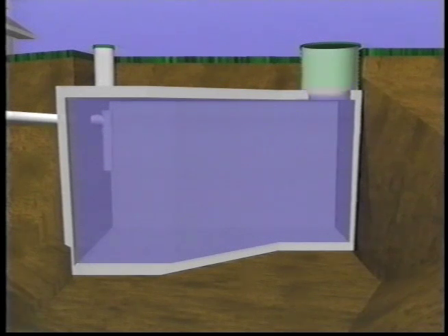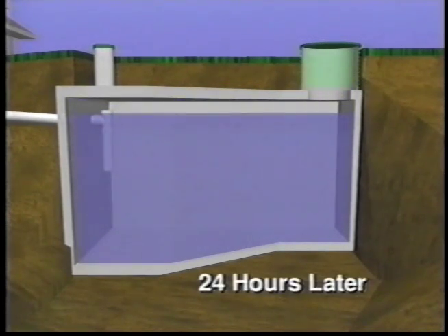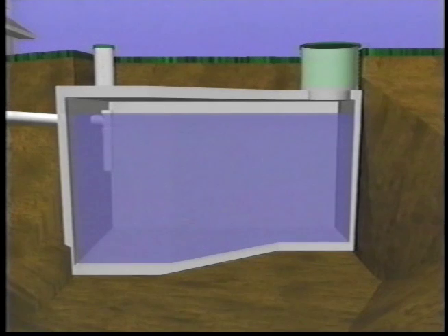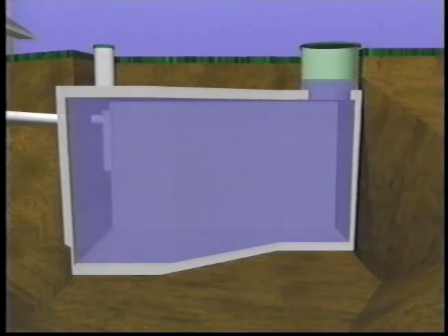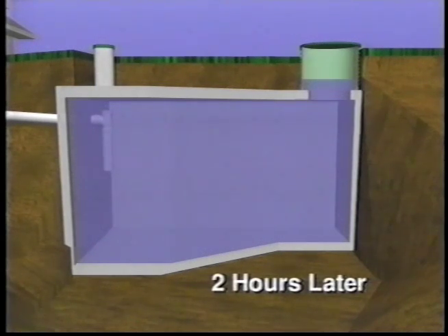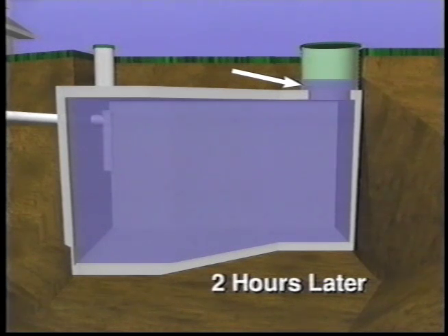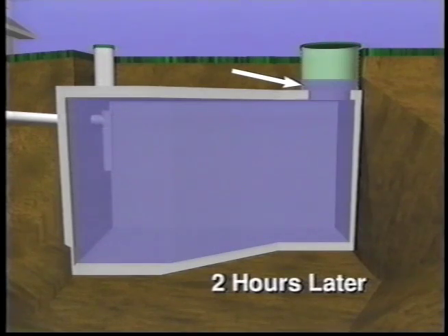A new concrete tank will absorb water, so let the tank sit for 12 to 24 hours and then refill it to two inches above the riser. When you check the water level again, after waiting at least two hours, it should be two inches above the riser. If it is lower, you have a leak in the tank or riser and will need to take corrective action. Absolutely no leakage is acceptable.